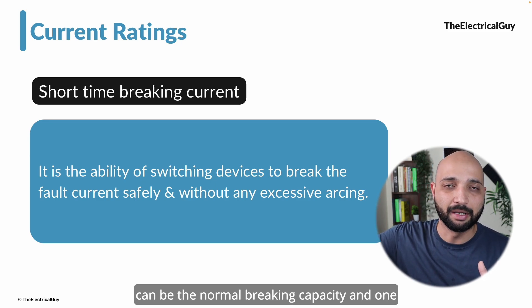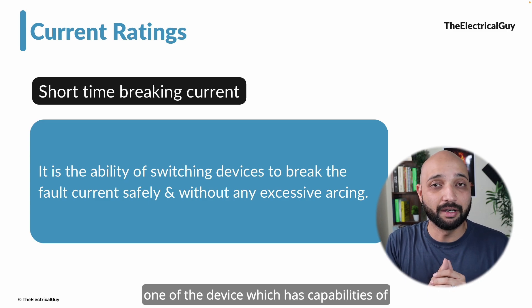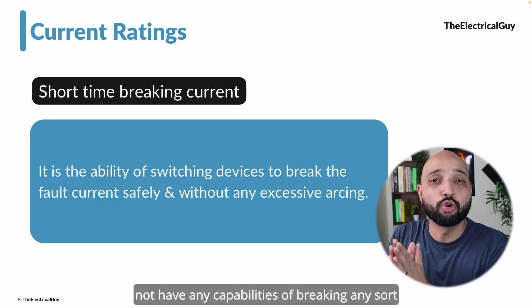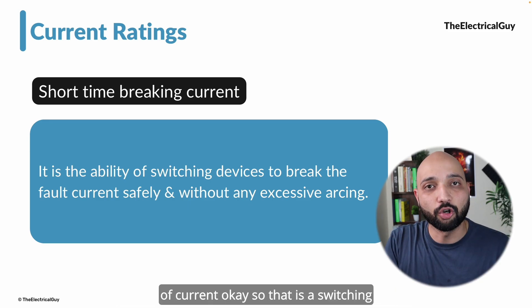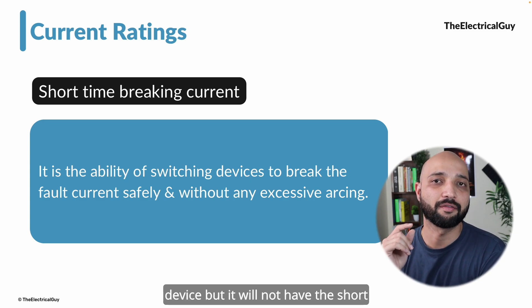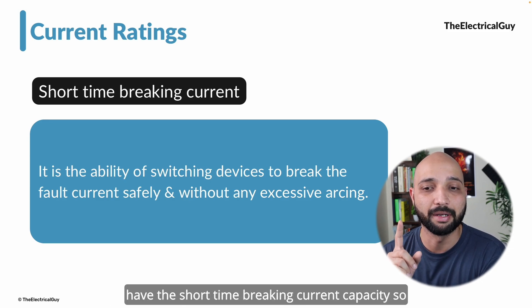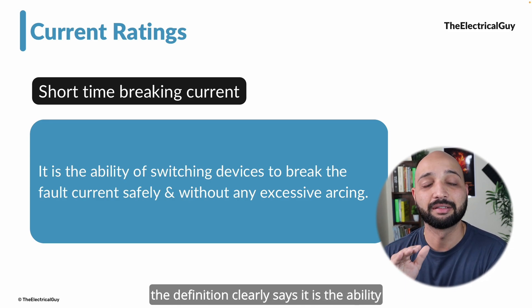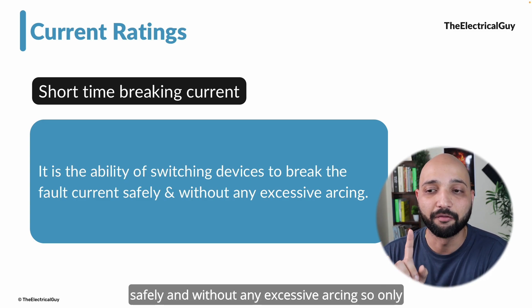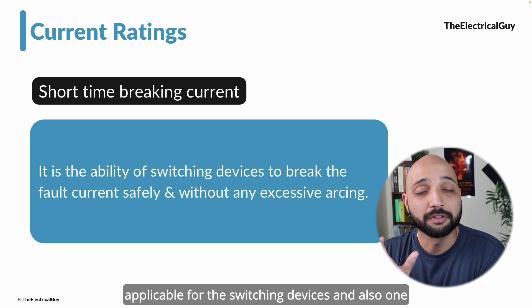Breaking capacity can be normal breaking capacity or abnormal breaking capacity. A circuit breaker is one device which has capabilities of both. If we talk about a disconnector, it does not have any capabilities of breaking any sort of current — so it is a switching device but will not have the short time breaking current capacity. Only a circuit breaker will have the short time breaking current capacity. The definition clearly states: ability of switching devices to break the fault current safely and without any excessive arcing.